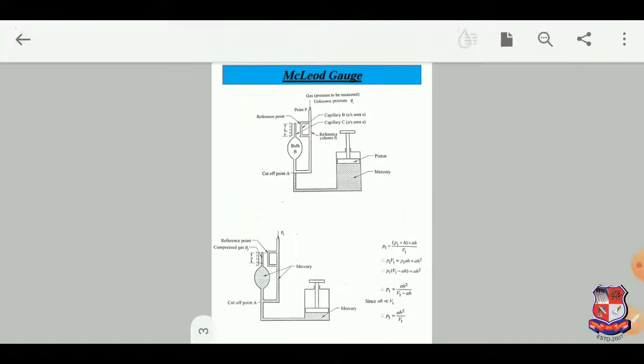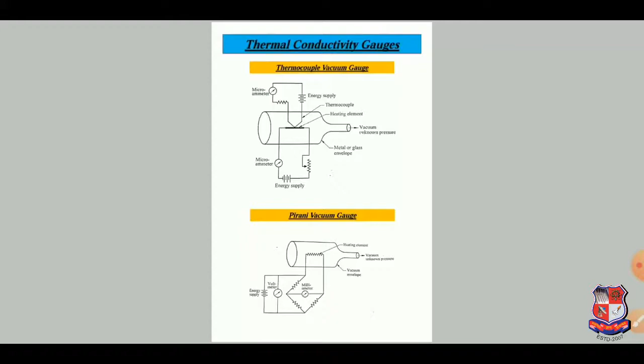So this is the McLeod gauge. Next is thermal conductivity gauges. After the McLeod gauge, there are thermal conductivity gauges. At low pressure, the thermal conductivity of a gas, the ability of a gas to conduct heat, has a direct relation to pressure. The relation between change in thermal conductivity and change in pressure works over a pressure range of 10⁻⁴ to 10⁻² torr. So this principle is used in thermal conductivity gauges to measure pressure of gas.